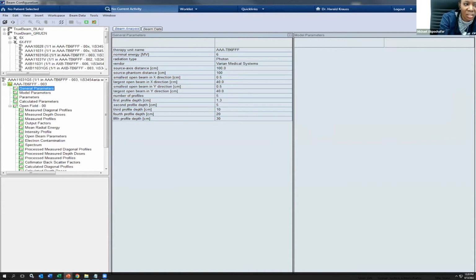Okay, so these are all the things that we need to do, and this is just a sample of the 6 X flattening filter free. That is the 6 energy photon, the flattening filter free. Now we do all this. We input all this data for the general parameters, the model parameters, all these parameters, and we have to import data for each of the energies: the measured diagonal profiles, the depth doses, output factors, and like that. So that is why it takes a lot of time.